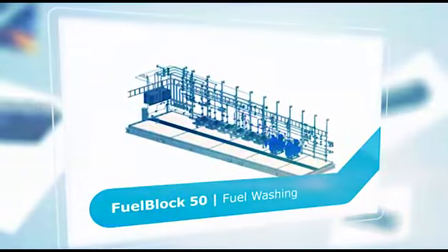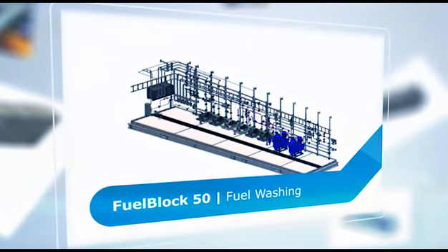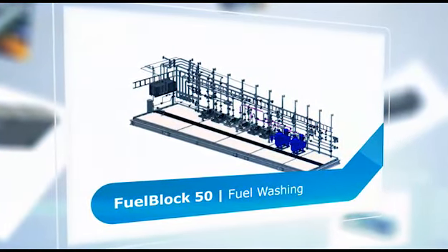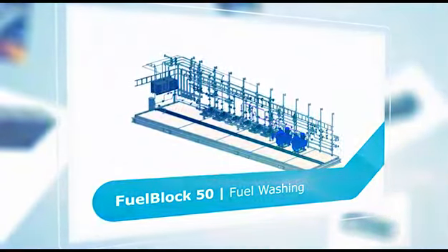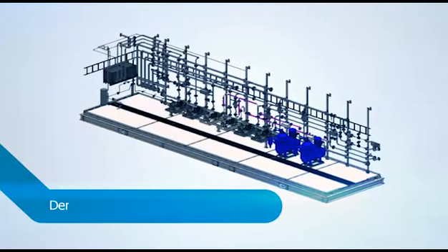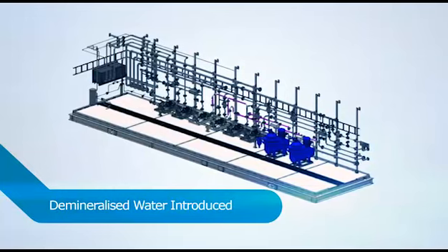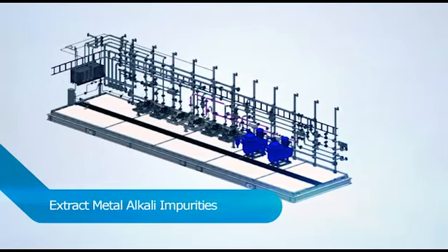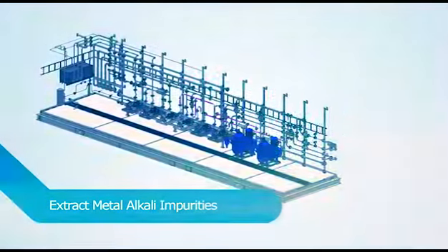Impurities such as sodium or potassium may be present in raw fuel, which cause corrosion in a turbine's combustion section. Fuel washing is a process where demineralised water is introduced to the centrifuge feed to dissolve and extract the metal alkali impurities from the fuel.